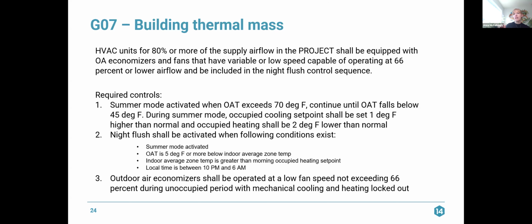The night flush is activated when the following conditions exist. Summer mode is activated. The outdoor air temperature is 5 degrees or more below the indoor average zone temperature. So if we have a cooler, warm summer night, it's 55 degrees outside and it is an average of 70 degrees in the spaces, this would be when the night flush is activated. The indoor average zone temperature is greater than the morning occupied heating set point. So your morning occupied heating set point would be 68 degrees, and we would be able to flush out to get from that 70 to 68.